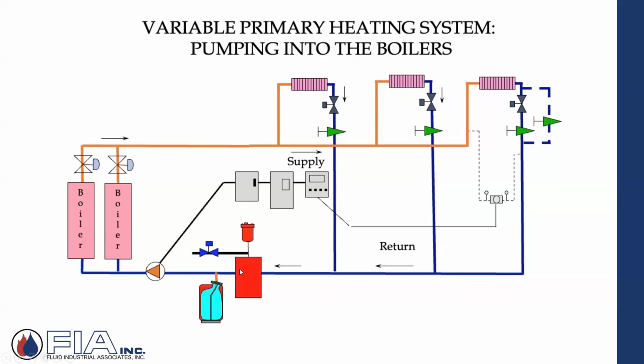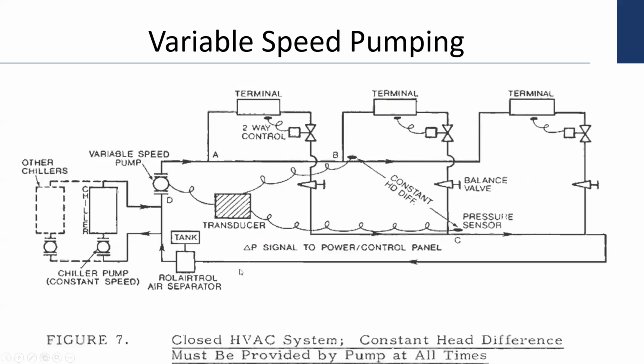Yeah, primary, secondary versus maybe variable primary. So I don't have that primary, secondary connection. My primary pump, if you will, is providing flow. In this case, the label is boilers. It could be boilers or chillers. It's the same distribution pumping that's going through all of my terminal units. Back here, it might have been production, or a primary for my chillers or boiler plant.